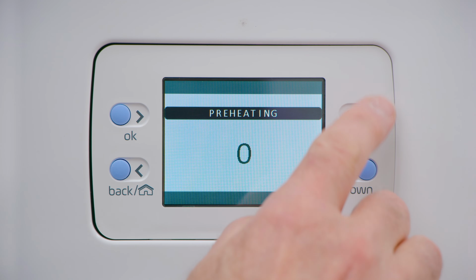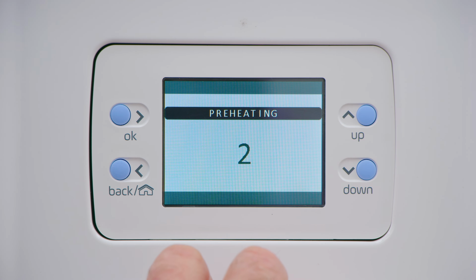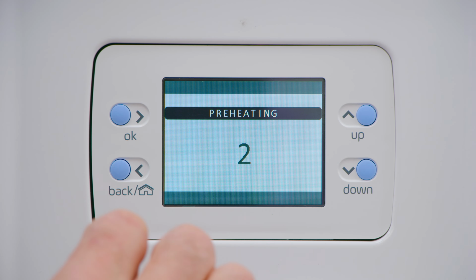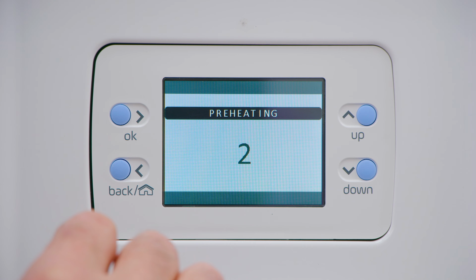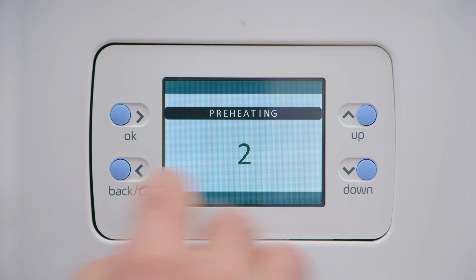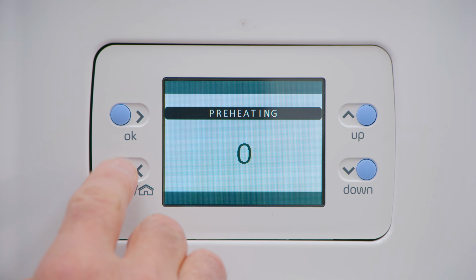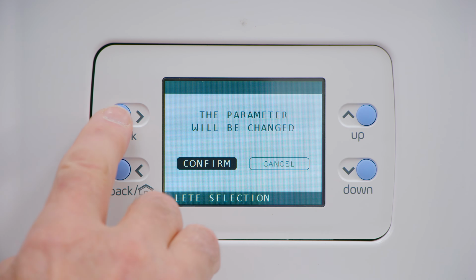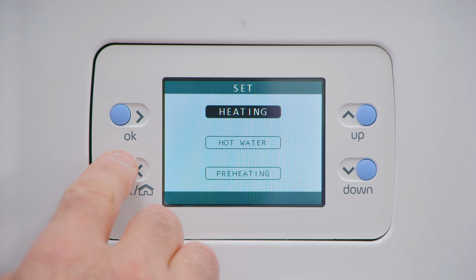If we select option 2, it's touch and go preheat. What will happen then is there will be no continual preheat, but before the customer uses domestic hot water, a very brief opening and closing of any hot tap in the building, the boiler will preheat for 1 cycle only, and then it won't preheat again until another brief opening and closing of a hot tap.